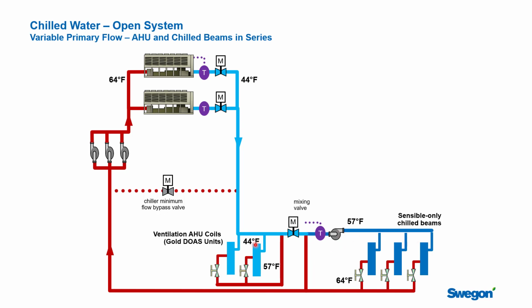And so the conversation comes around to, hey, could I take my water and flow it through the air handling units first, and then after that, take that water and run it out through my chilled beams, which are sensible-only, and I need the water temperature to be above the dew point of the space. And then I would get a very large delta T across the plant, which is really helpful for improving the chiller plant design. And it's particularly helpful around the hydronic system in terms of sizing the pumps and the piping throughout the building.